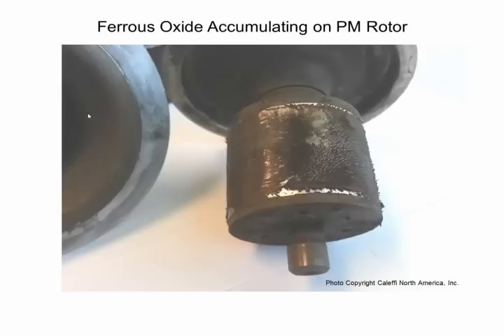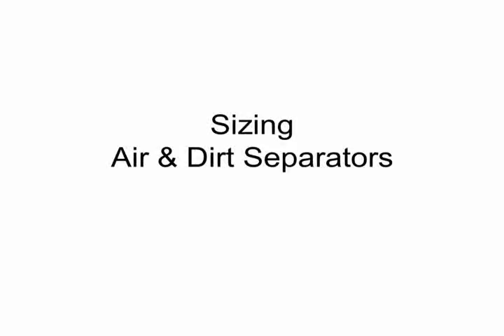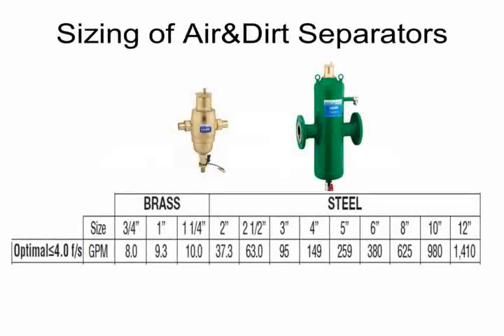Now, does that mean that the pump's going to fail? No, not necessarily. But as this builds up over time, and if you're working under a delta P mode, that pump is going to maintain your delta P, but it's going to work a little harder, perhaps consuming a little bit more wattage than you'd like to accomplish the flow rate that it was set for. So we especially like these when you have very efficient heat exchangers and ECM pumps to use this magnetic type of a separator.